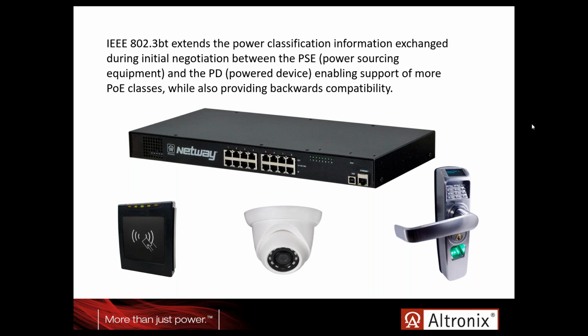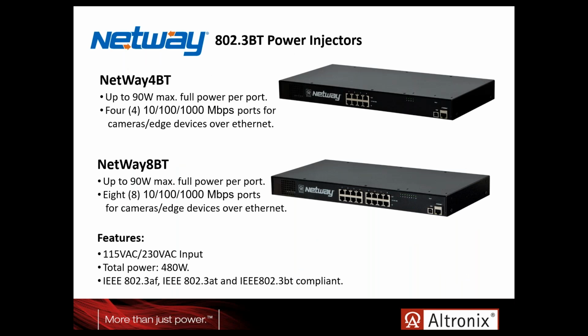That means you can plug any power device into a PoE switch or mid-span injector that works to the 90-watt standard, but the power sourcing equipment will only pass the power that's required for the PD. So if it asks for 15 watts, that's what it'll get, or 30 watts, and so forth. Altronix has a number of power sourcing equipment models on the market.